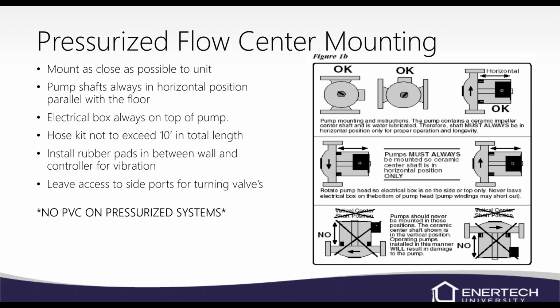Make sure that the pump shafts are always in the horizontal position, so parallel with the floor. Electrical box, make sure it's on the top. If you turn the flow center upside down and don't move the electrical box to the top, what will happen if they do condense and sweat? There's a lot of humidity in the building or something, or sometimes that water temperature is just the right temperature and it will sweat. Well, that water could actually run down and sit in the electrical box, and then it could fill up the electrical box and short out the connectors there. So if we have it on top, the water can't stay in that box. It'll run to the bottom and drop off the bottom of the pump. So make sure the electrical box is always on the top, no matter what position the flow center is in.